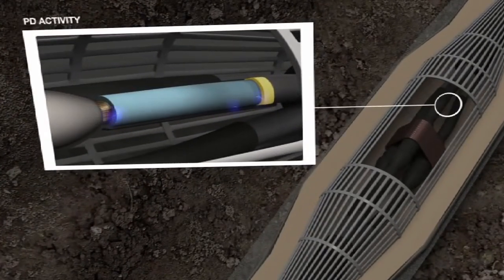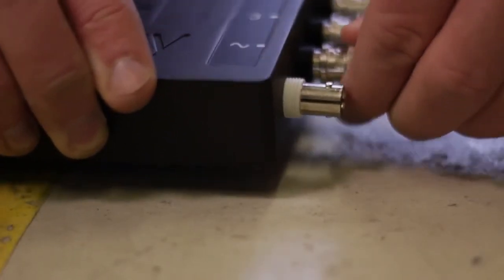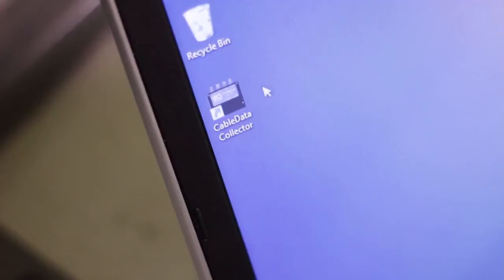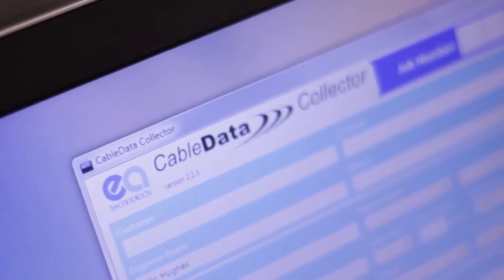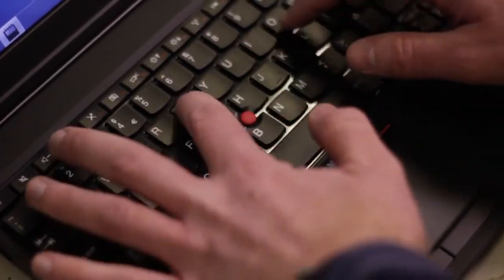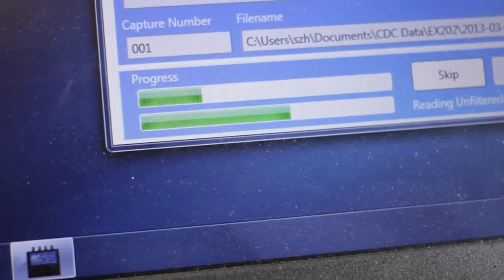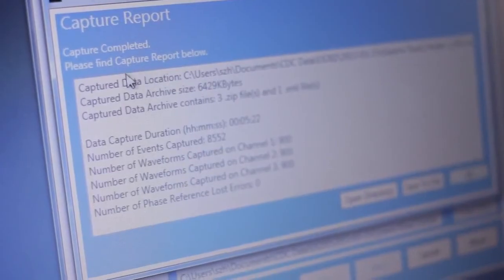So, the Cable Data Collector provides a fast and accurate health check for all your distribution voltage cables. It's easy to use. It works on live cables up to several miles in length. Expert analysis gives you the information you need to identify defects and prevent outages, and plan maintenance and replacements more efficiently. And finally, using the Cable Data Collector to test for PD activity will indicate when cables are working correctly and don't need maintenance or replacement.